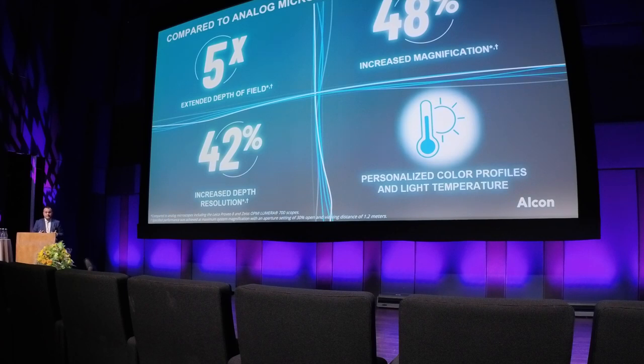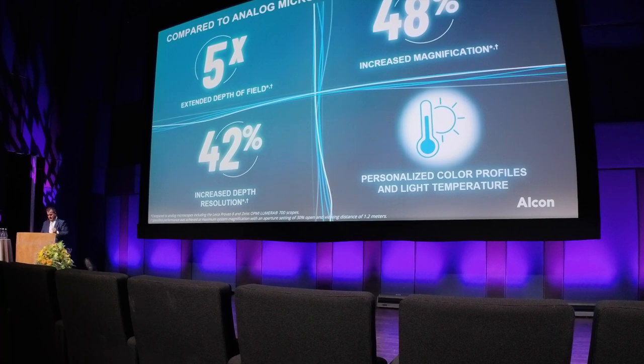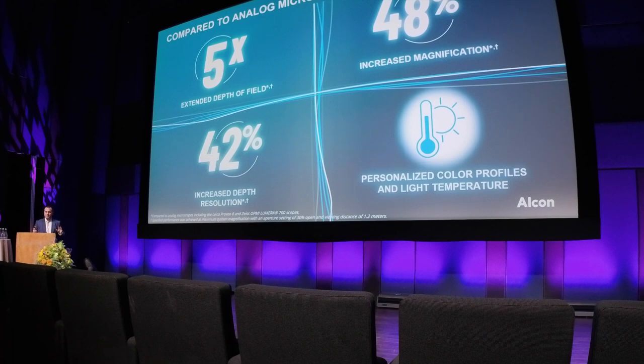High-quality precision: it gives you a five-times extended depth of field. You can have a 48% increase in magnification on top of your microscope's magnification, which is definitely beneficial. You can have increased depth resolution, meaning that across all the depth of field you see with equal resolution — something that is not the case with an analog microscope. You can also have personalized color profiles and create your own digital filters, giving you limitless opportunity to modify the image.